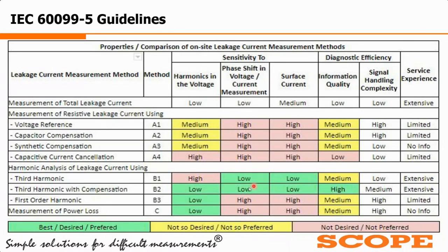So phase shifting should be as low as possible. And during this measurement, I want to know the internal condition of the ZnO blocks. So whatever the effect of the surface current is during the measurement, if it is minimum, that should be preferred. So here once again, low is preferred. And if the quality of information I am getting during the measurement is high, that is preferable. So in totality, as you can see clearly, in this B2 method, third harmonic with compensation, this is the ideal way of measurement.